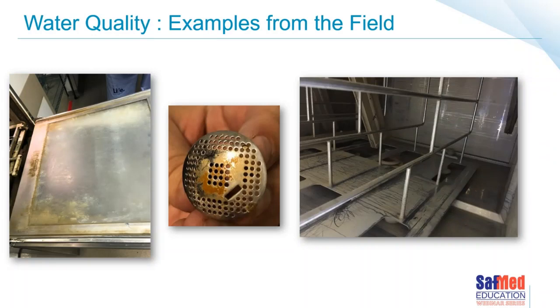These are pictures taken in the field over the years of the inside of some automated washer disinfectors. The picture in the middle is actually the drain sieve from an ultrasonic cleaner — there's a build-up of grime. On the left is a really grimy build-up of heaven-only-knows-what substrates within the chamber of a washer disinfector because of really challenging water quality — in that sieve we even found some gravel and soil. The one on the right looks more like hard water spotting from hard water minerals.